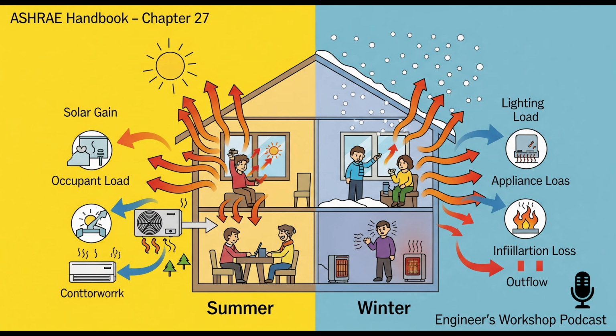And it all comes back to people feeling comfortable, right? Absolutely, occupant comfort is paramount. The handbook references ASHRAE Standard 55, the main standard for thermal comfort. For colder places, it specifically recommends double glazing if the winter design temperature is below about 7 Celsius or 45 Fahrenheit. Why double glazing specifically? To reduce cold drafts near the window, make it feel less cold radiating inward, and crucially to prevent condensation on the glass when you have normal indoor humidity levels. High-performance windows can seriously cut down cooling loads compared to old single panes too.